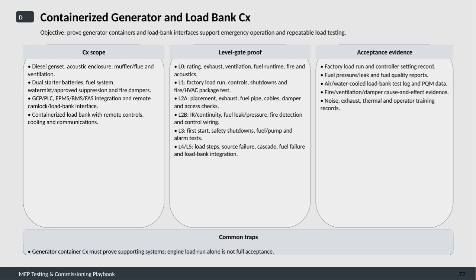For acceptance evidence, documentation is critical. This includes factory load run records and controller settings, fuel pressure and leak reports, as well as fuel quality tests, load bank performance logs and power quality measurements, fire and ventilation cause and effect analysis, and records of noise, exhaust, thermal performance, and operator training. A common pitfall to avoid is assuming that a successful engine load run alone represents full acceptance of the generator container. Instead, commissioning must prove all supporting systems function properly to ensure the system is fully operational and reliable.